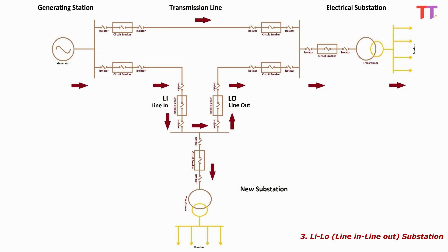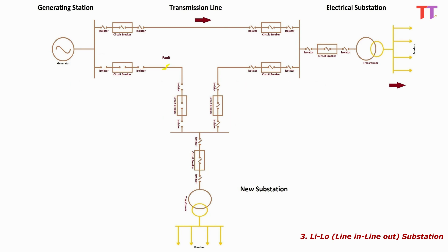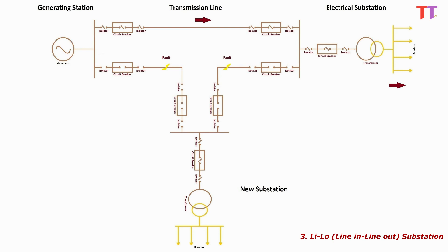This line in and line out layout is called LILO. Power flows in the same direction as before, adding the extra load of the newly constructed substation. This type of layout is more reliable than the previous two layouts, because in case of fault on one line, the other line continues to supply power, and vice versa. However, outage or breakdown of both lines at the same time does affect the connected load.